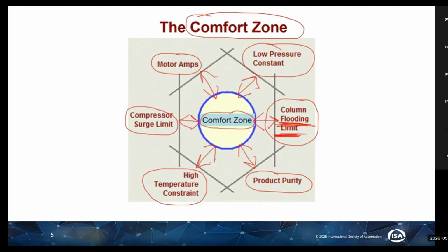On the other hand, I have a constraint. One of these constraints is motor amps. You can see here, for example, the controller is having a high variation. If I increase the speed, it may touch the high limit and trip the plant. So that's why we always run the plant in the comfort zone, away from the optimization set point, which is near to the constraint.